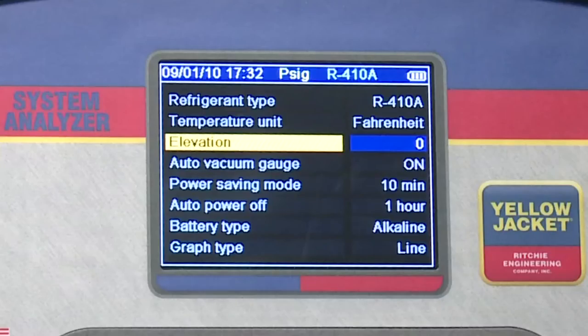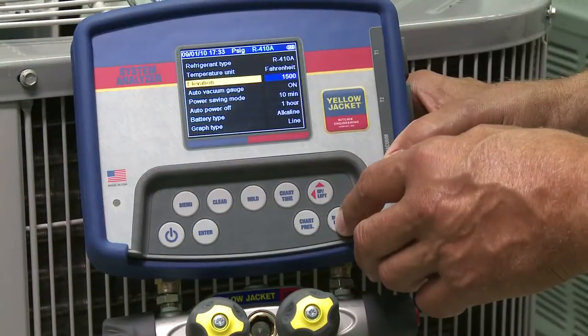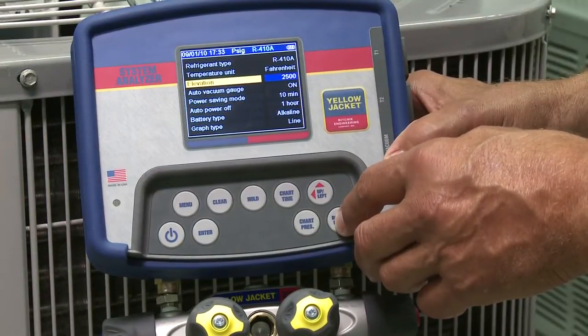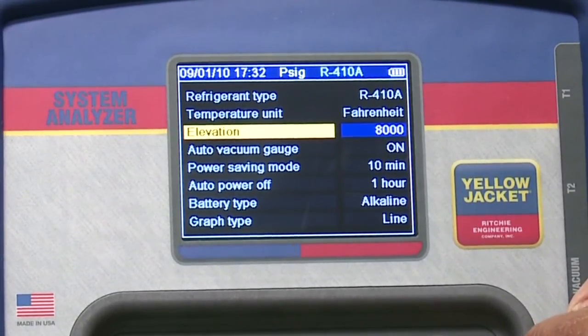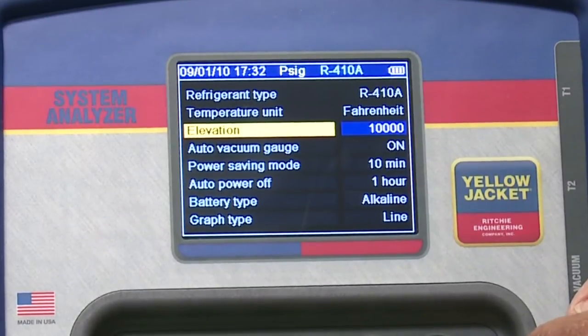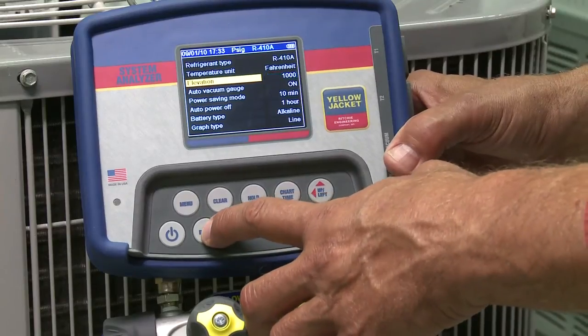While on this screen, let's also set the elevation. A nice feature with this unit is that you can adjust for elevation changes without zeroing under vacuum. The default setting on the analyzer is zero, or sea level. If you're working at a higher elevation, you'll want to change the setting to get the most accurate PT chart calculations. Elevation options are in increments of 500 feet until you reach 5,000, after which they increase by 1,000, with a maximum elevation level of 10,000 feet. Once you've reached the number closest to your elevation level, press enter to set.